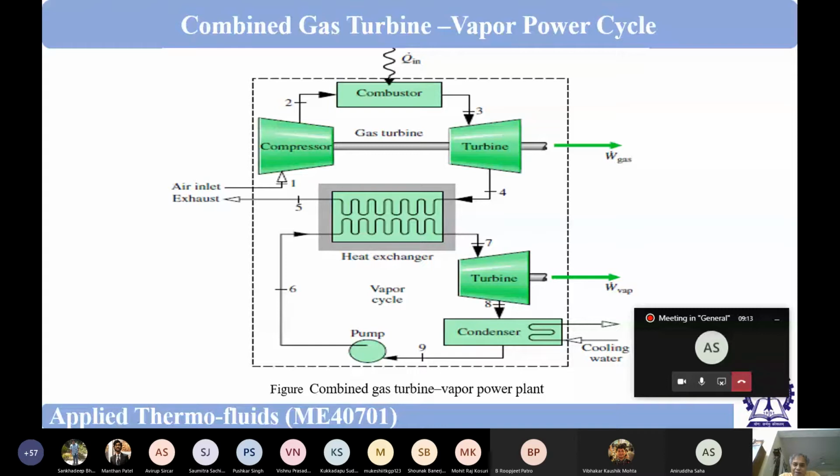Then, if we have to have a steam turbine power plant, its installation takes a large amount of time, as the power plant is very big. Whereas a gas turbine power plant is small and very quickly you can install it. And then the same thing regarding load fluctuation: a gas turbine power plant can cope very well, whereas a steam turbine power plant is sluggish and takes time.